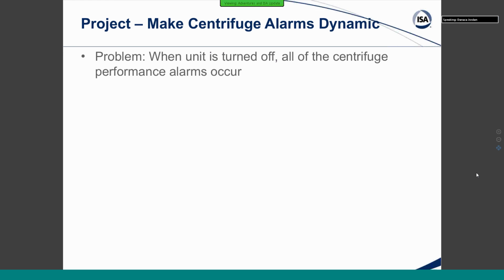On a non-capital side, one of the ones that has also gotten us a lot of thanks in our department is turning off centrifuge alarms. Basically, we have several performance alarms on our centrifuges, things like high or low torque, or if the vibration gets out of range, just a couple of different indicators that tell us when the centrifuge is operating poorly. Unfortunately, the way it was set up, whenever the unit is turned off for the daily cleaning, all of those alarms would occur all at once, and they would stay on until the unit was put back into service. So this became quite a nuisance with a lot of our operations.